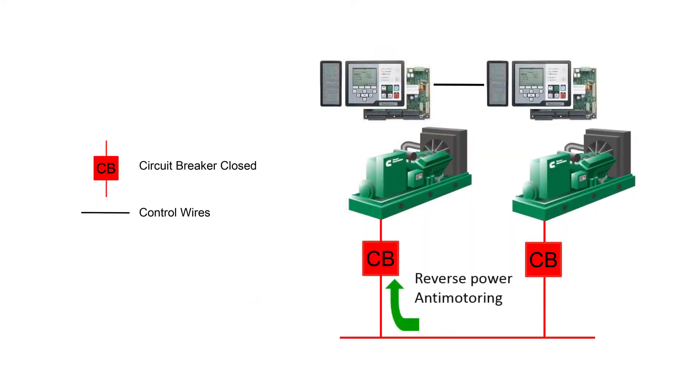In this video we will focus on generator set protection and Amp Sentry. Local codes and standards stipulate that generator sets must be protected from the effects of short circuit and overload conditions. There are two very important protection elements in parallel generator sets: reverse power or anti-motoring, and under excitation or loss of field.